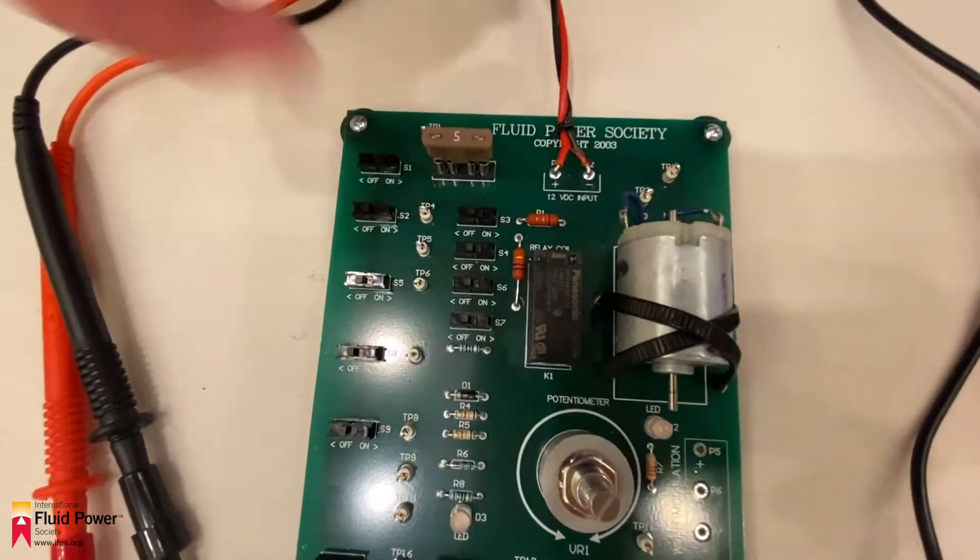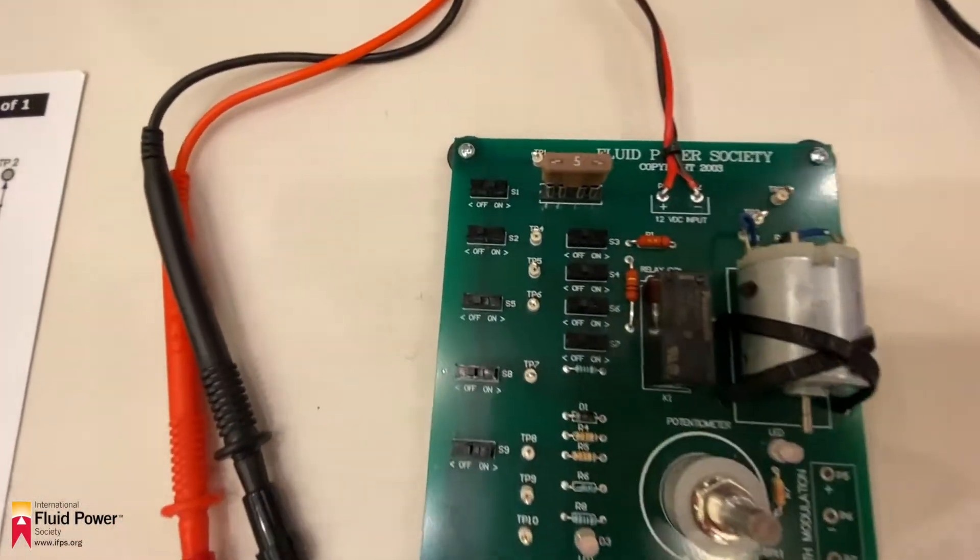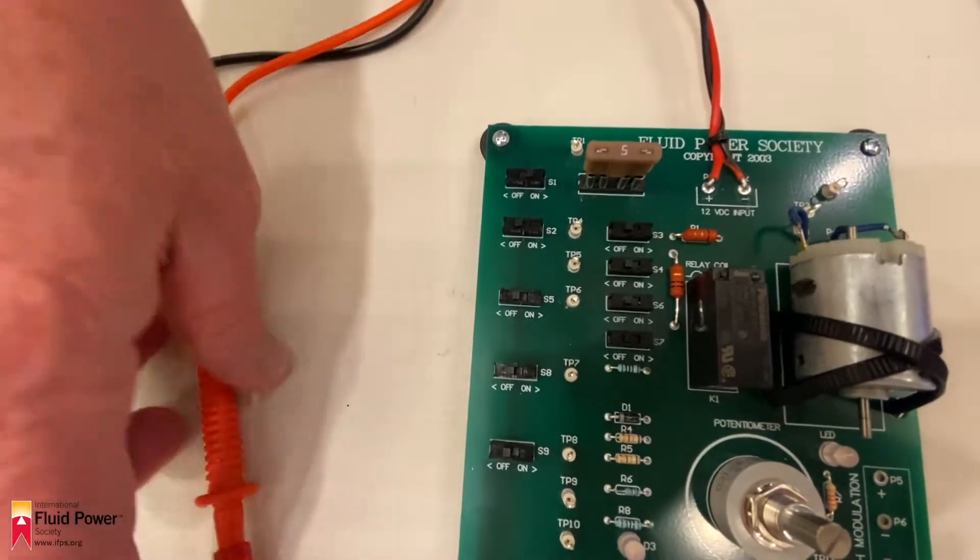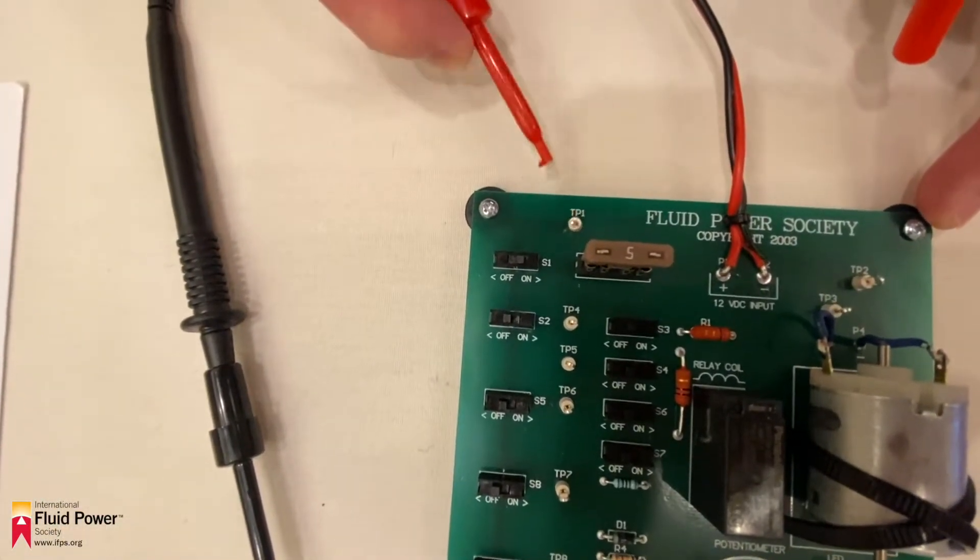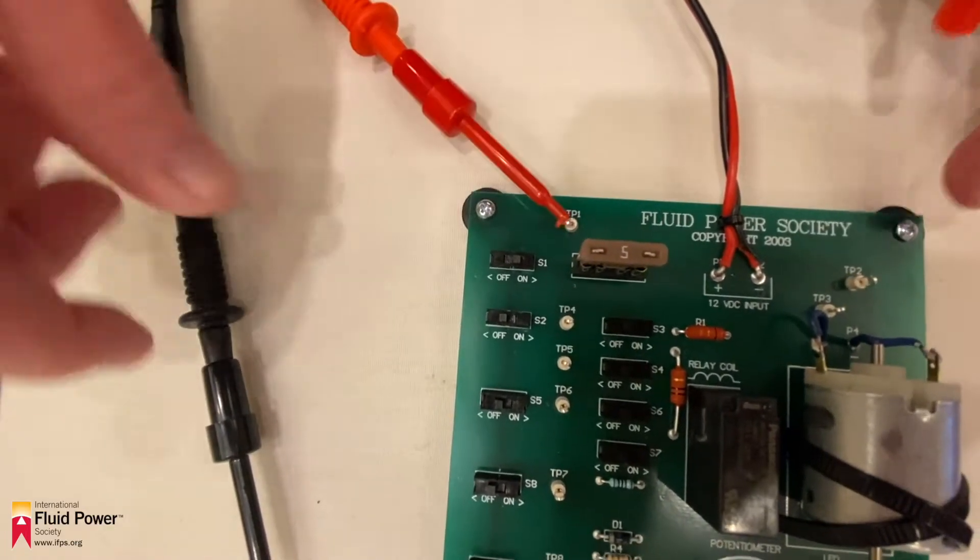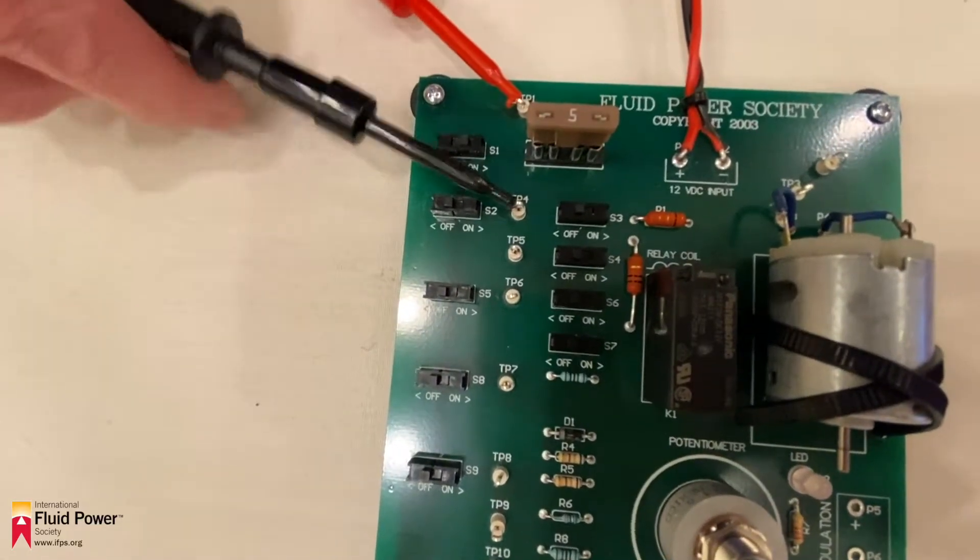Always measure with S1 in the closed position. Always place the red lead of the amp meter on TP1. Always leave the first switch open on the rung of the circuit being tested. Always place the black lead on the first test point after the open switch.